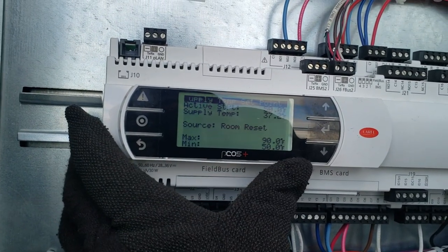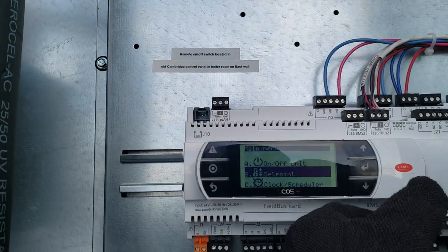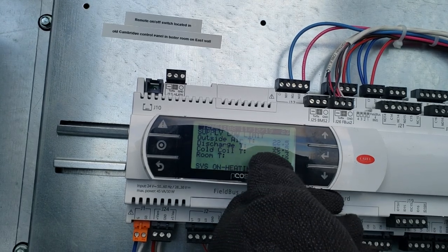We're checking our set points. So far this thing's pretty user-friendly. Currently it looks like the active set point is 50. Supply temp's 36. Outside air was 22, discharge was 32, cold coil 22, room 78. System on heating. Pretty much the same thing both times.